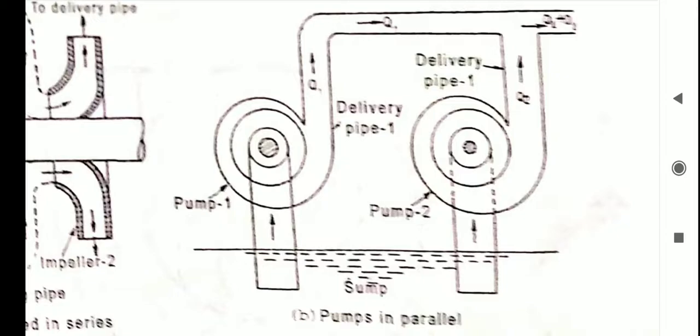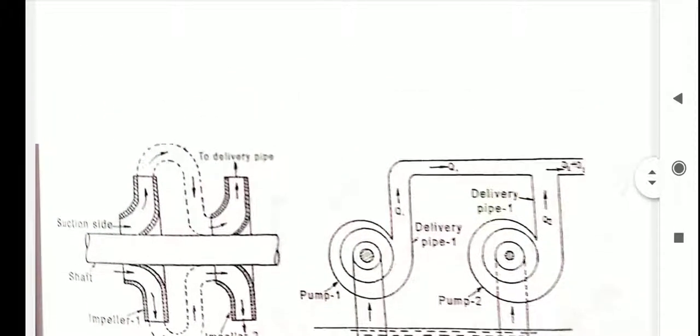For identical pumps working under the same head, the discharge will be the sum of the flow rates of each pump. If the number of identical impellers each delivers the same flow rate which works under the same head, then the total discharge from the multi-stage pump is given by total discharge qt equals n into q. This is about pumps connected in parallel and pumps connected in series. This is about multi-stage pumps. Thank you.